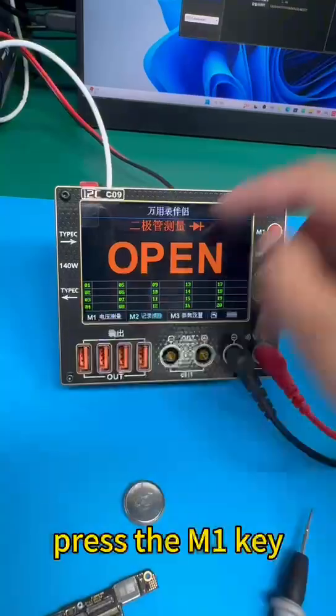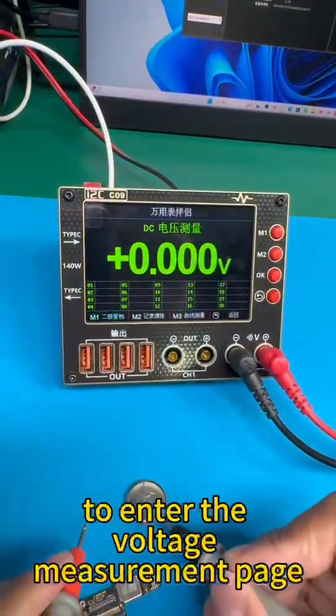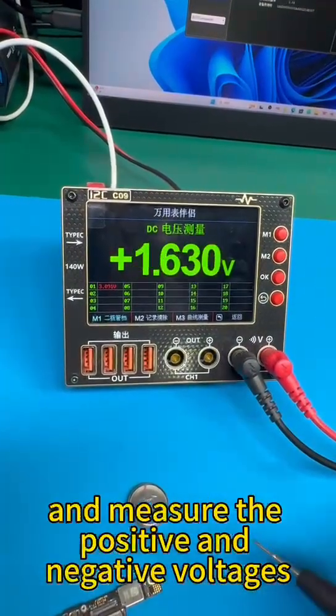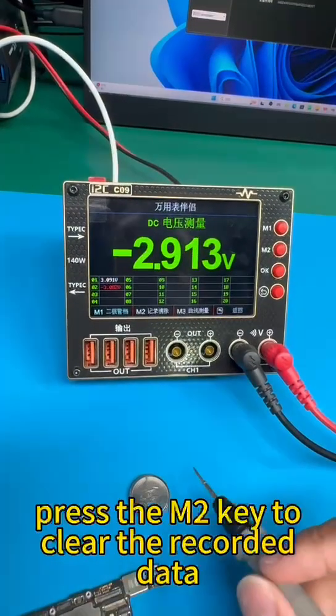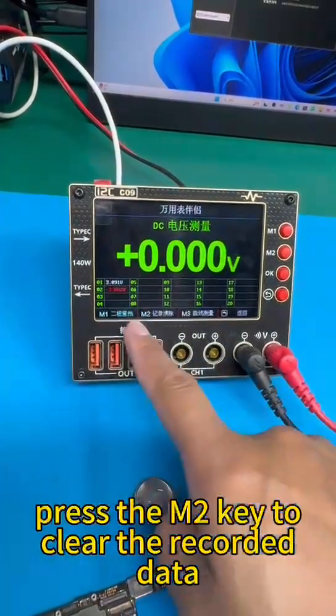Press the M1 key to enter the voltage measurement page and measure the positive and negative voltages. The measurement data will also be recorded. Press the M2 key to clear the recorded data.